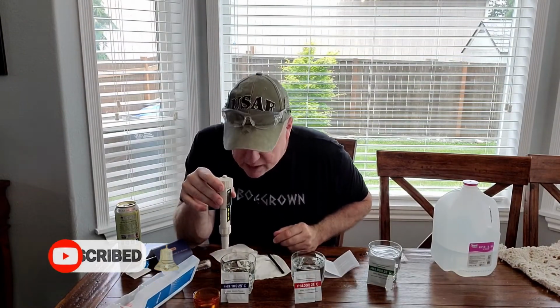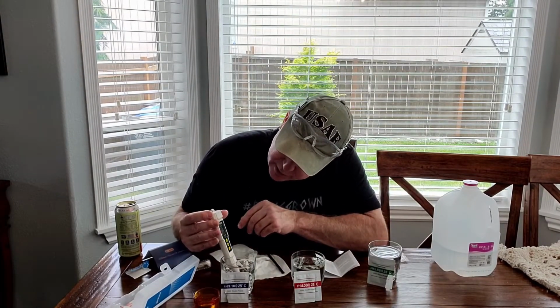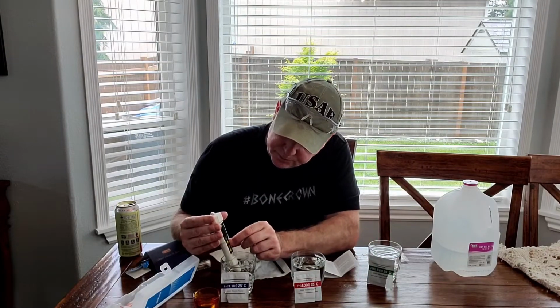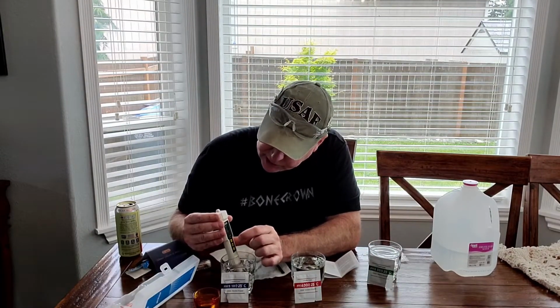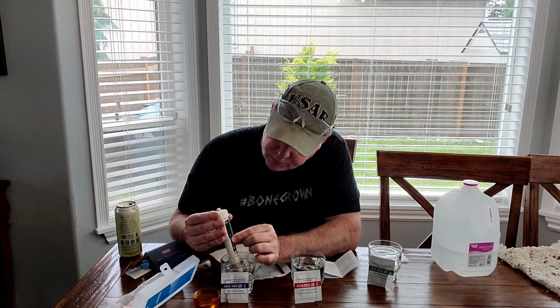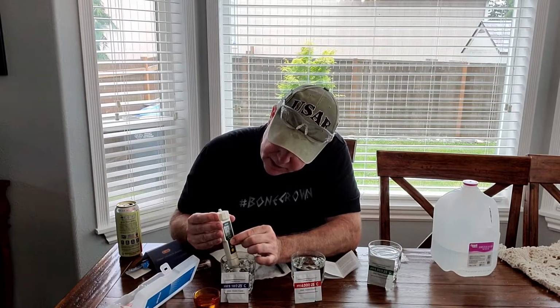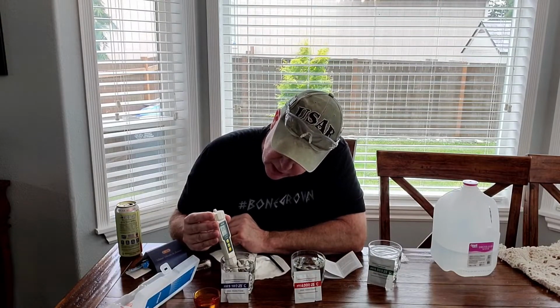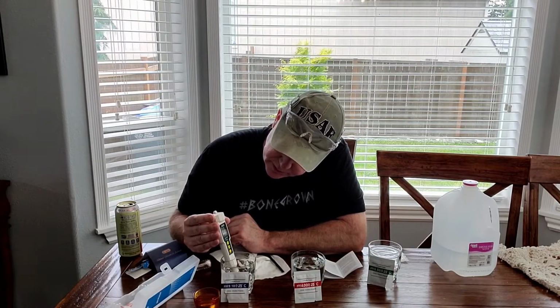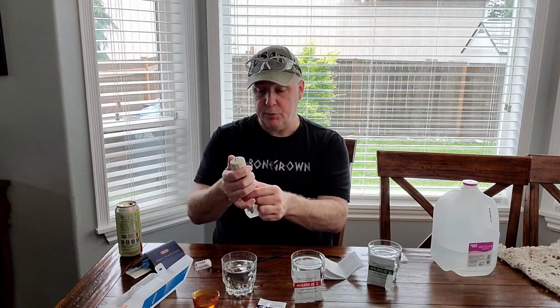So now I don't see anything in there, so we're going to do the final calibration at the 9.18. So I'm going to go ahead and turn it on, and again you're going to see it come on, and it's pretty close. And we're going to let it stabilize, and I'm going to hit the calibrate button one more time till calibrate comes on, and then I'm going to release it. Now it's going to go through auto calibrate, SA, end. So now I'm hitting at 9.18. So I've got all my numbers. So right there, I'm on my money. So I'm good. I'm happy with what I'm calibrating.